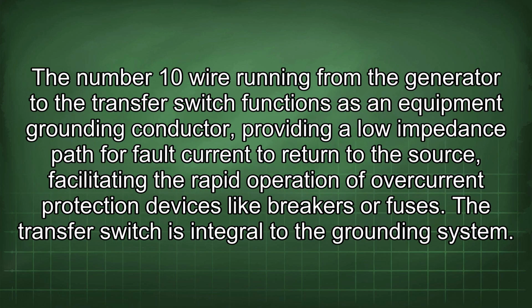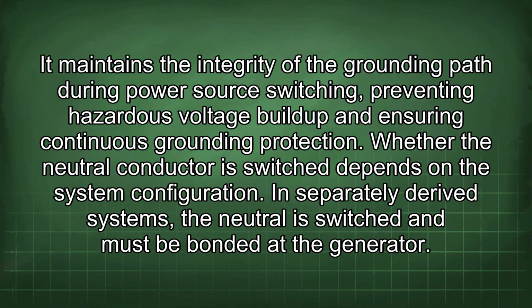The number 10 wire running from the generator to the transfer switch functions as an equipment grounding conductor, providing a low impedance path for fault current to return to the source, facilitating the rapid operation of overcurrent protection devices like breakers or fuses. The transfer switch is integral to the grounding system. It maintains the integrity of the grounding path during power source switching, preventing hazardous voltage buildup and ensuring continuous grounding protection.